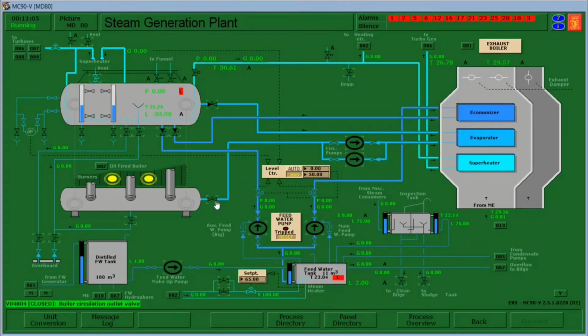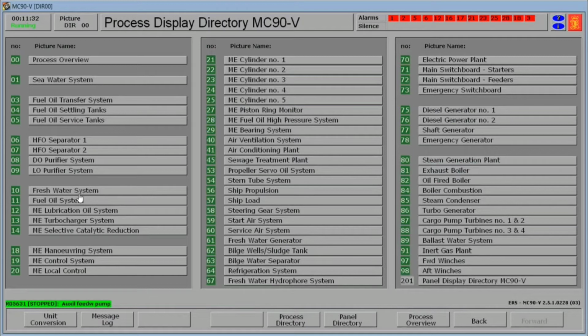Open the circulation outlet valve and the inlet and start one circulation pump. Open main feed water discharge valve. Set the manual to 0. Turn on the main feed water pump and set level control to auto. Now, while waiting for the temperature and pressure, we proceed to and prepare some systems.